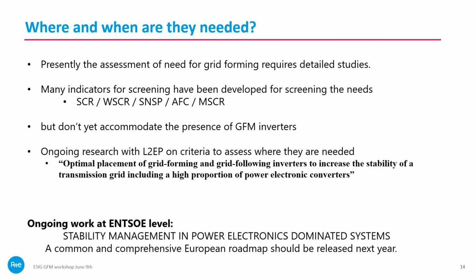Presently there are existing indicators like SCR, weighted SCR, and SNSP available, but they don't really accommodate the presence of grid forming inverters. When you start installing grid forming inverters, you don't see their impact on these indicators, or know if these indicators are really suited to take into account the impact of grid forming. So there is already a PhD just starting with L2EP, a lab in the north of France, on optimal placement of grid forming and grid following, and also to develop these indicators.